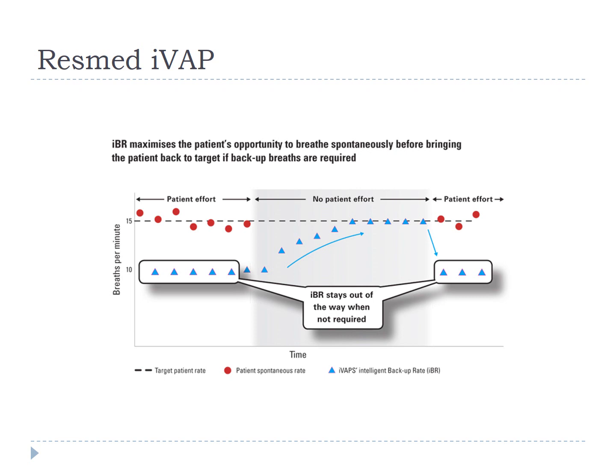So this device maximizes the patient's opportunity to breathe spontaneously before it starts to give the patient a backup pressure. So you see the blue triangles start out at a rate of 10, and when the patient isn't taking a breath, then it kicks in and it increases with the backup rate, and then when the patient's effort comes back, you see then that pressure backs off and lets the patient breathe on their own effort. So again, this is a slower response time, but it's ensuring that the patient gets the appropriate tidal volume or minute ventilation. Let's go on.